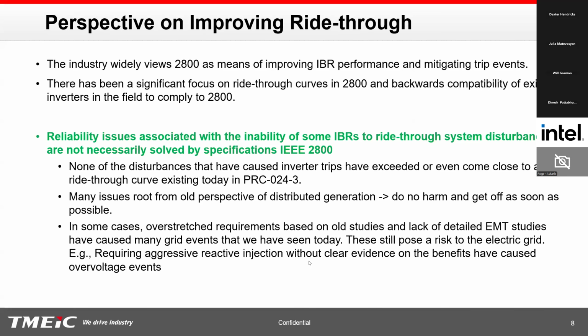There is a lot of focus on voltage ride-through requirements in 2800. Based on our experience, we had inverters trip during grid events in ERCOT and other locations. None of our inverter trips have actually exceeded any of the voltage ride-through curves specified, even in PRC-024. The curve in PRC-024 is narrower than 2800, and none of the events even came close to any of these curves. Most of the events in the field that caused inverter trips are 3-cycle, 4-cycle fault events.